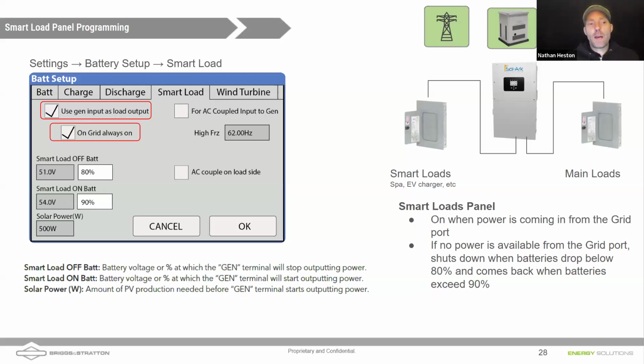And then it'll allow those batteries to charge back up, hopefully off of solar or another means, right, off of the generator, if you have it on the utility port, until it gets above 90%. And I misspoke there. Even if you have a generator on the utility port, that sub panel would always be on when that generator comes on.